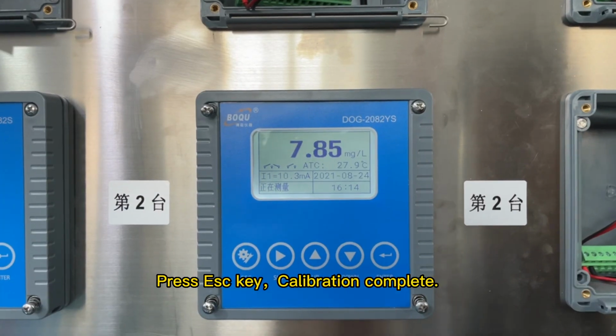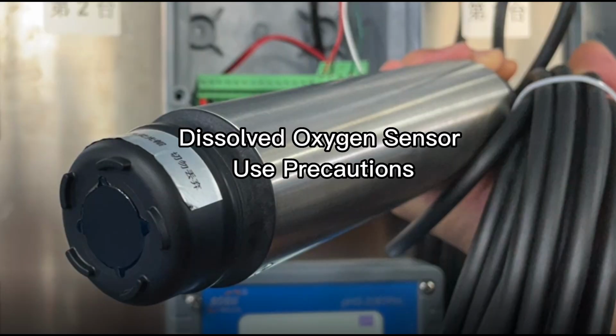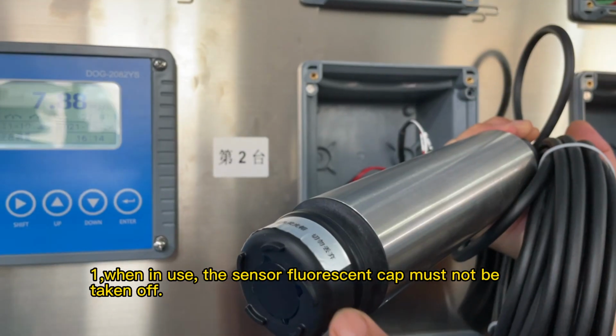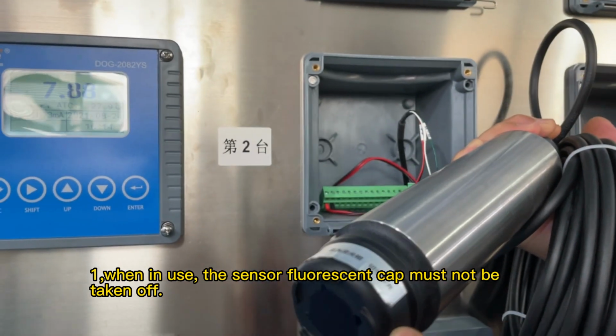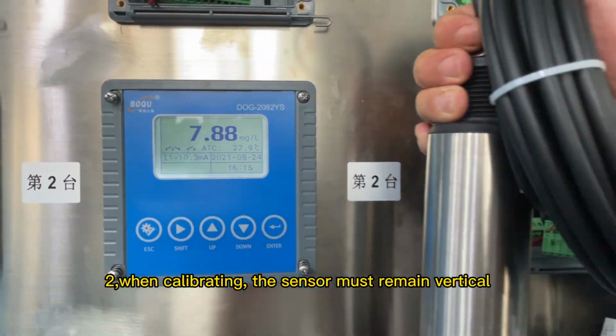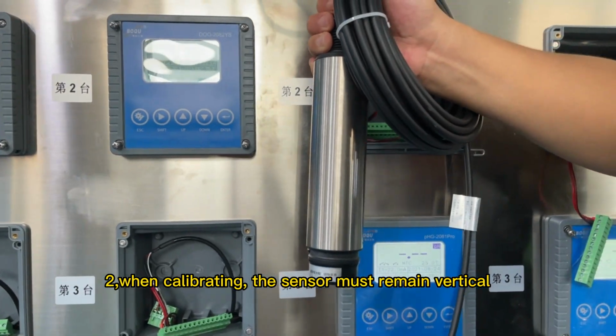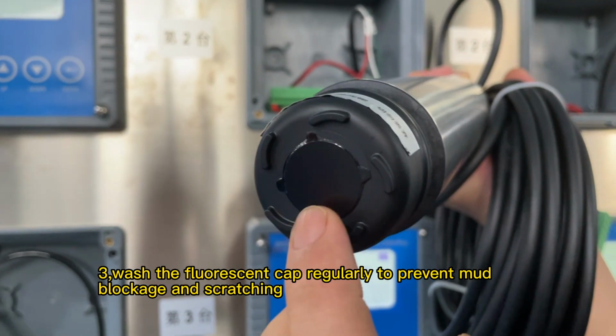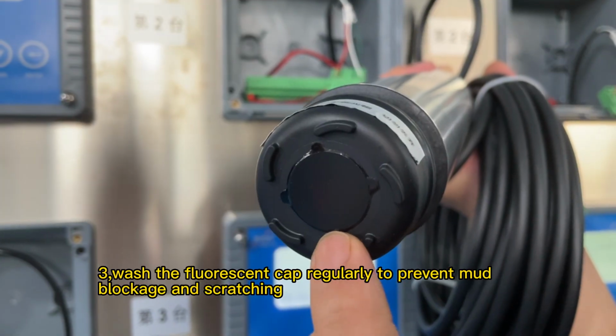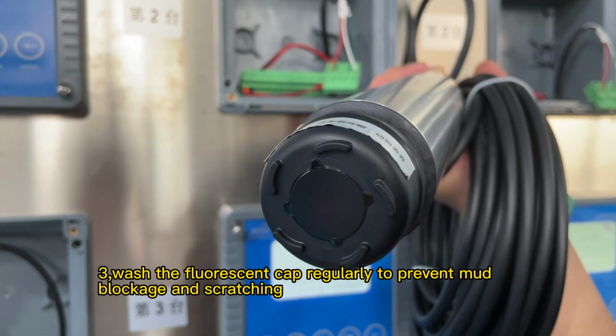Calibration complete. Dissolved oxygen sensor use precautions. 1. When in use, the sensor fluorescent cap must not be taken off. 2. When calibrating, the sensor must remain vertical. 3. Wash the fluorescent cap regularly to prevent mud blockage and scratching.